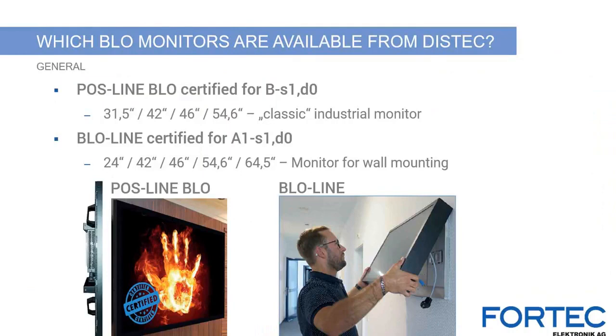Distec offers two versions of fire load optimized monitors. The POS-LINE BLO is certified for fire protection classification B S1 D0, meaning hardly flammable, little or no smoke development, and no burning dripping — with a more classic industrial monitor appearance. The BLO line monitor is certified for the highest classification A1 under DIN EN 13501-1, meaning non-flammable, and is flush to the wall to prevent flames getting behind the monitor. POS-LINE BLO monitors are available from 32 to 55 inches; BLO line monitors from 24 to 65 inches.